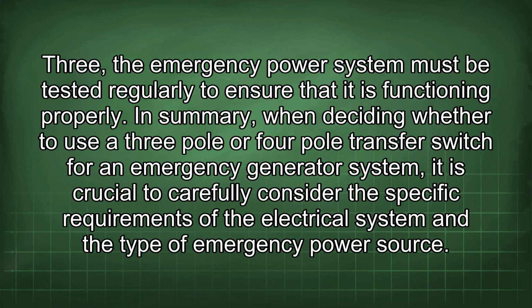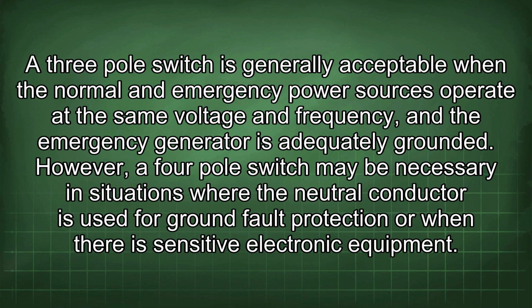In summary, when deciding whether to use a 3-pole or 4-pole transfer switch for an emergency generator system, it is crucial to carefully consider the specific requirements of the electrical system and the type of emergency power source. A 3-pole switch is generally acceptable when the normal and emergency power sources operate at the same voltage and frequency and the emergency generator is adequately grounded. However, a 4-pole switch may be necessary in situations where the neutral conductor is used for ground fault protection or when there is sensitive electronic equipment.